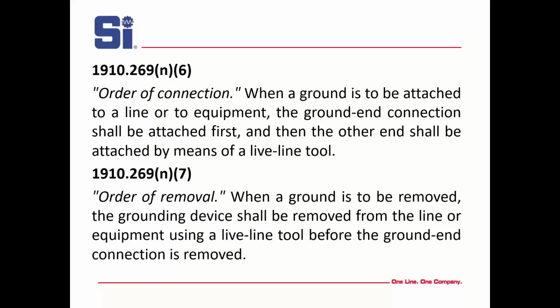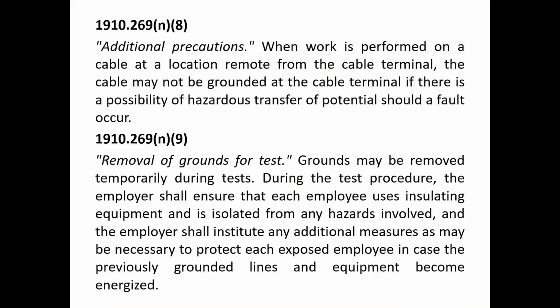The next two are very, very simple. Connect the ground connection first to the ground, and then you attach each phase. When you take it off, take off each phase, and the last one you take off is the ground connection. When work is performed on a cable location remote from the cable terminal, which could be a long cable, the cable may not be grounded at the cable terminal if there's a possibility of hazardous transfer of potential should a fault occur. In other words, they want you to go ground on the other end. That grounds the whole cable.